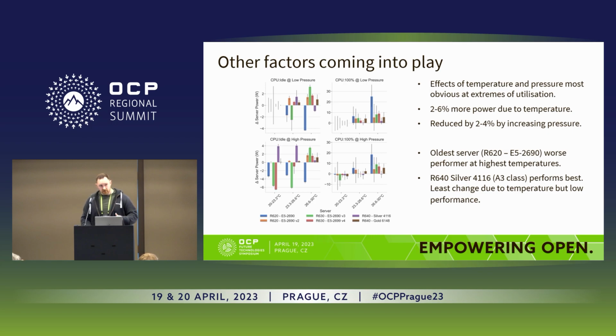What's really interesting here, and this is something that we didn't expect to find, there's an R640 Silver, so that's a 2017 server, Silver being the first generation scalable. It has the lowest performance of pretty much all the servers, but it is the most temperature tolerant. It's an A3 rated server. We rarely see these. That A3 rated server has no impact on performance or efficiency up to 40 degrees. That is massive, because if we can make all our future CPUs and models that temperature tolerant as we get from this mid-range 2017 CPU, we can actually play a very different game in emerging data center technologies.